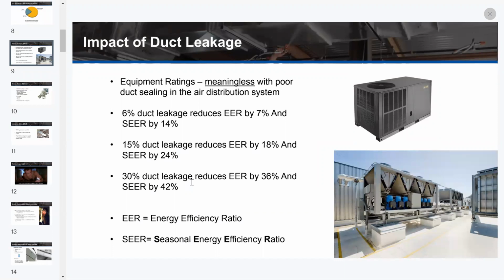All right, impacts of duct leakage. We know that all ducts have some degree of air leakage. We're not plumbers, and we would like to be eventually someday. But anyways, getting leakage down to a reasonable level is possible by using a good sealant and actually having the installing contractor trained on some of the key things about a proper application. When you look at equipment ratings, if you're looking at a rooftop unit, those equipment ratings can pretty much be kind of meaningless if you have a poorly designed HVAC duct system and it hasn't been sealed appropriately.